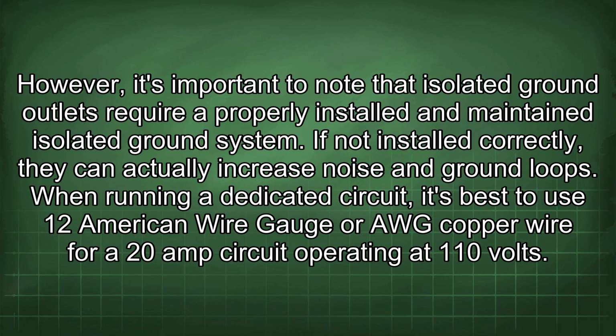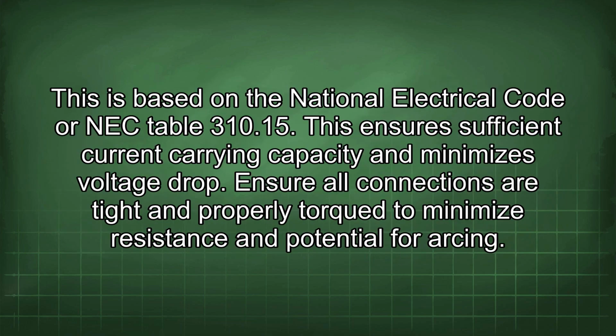When running a dedicated circuit, it's best to use 12 American wire gauge or AWG copper wire for a 20-amp circuit operating at 110 volts. This is based on the National Electrical Code or NEC Table 310.15. This ensures sufficient current carrying capacity and minimizes voltage drop.